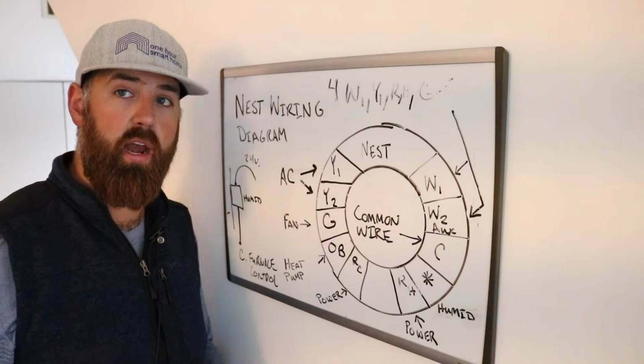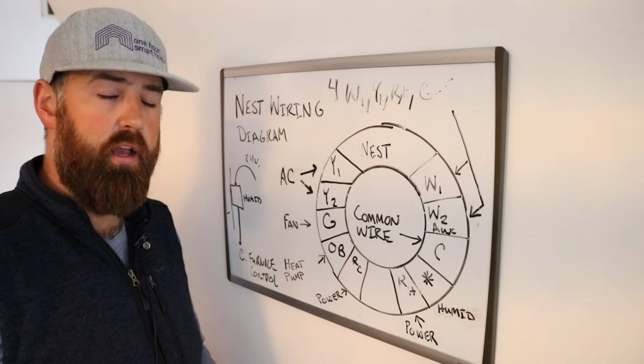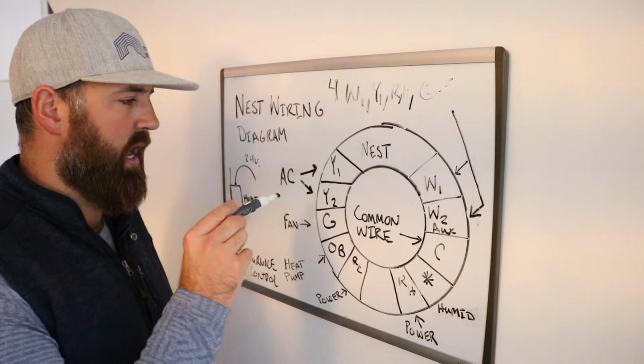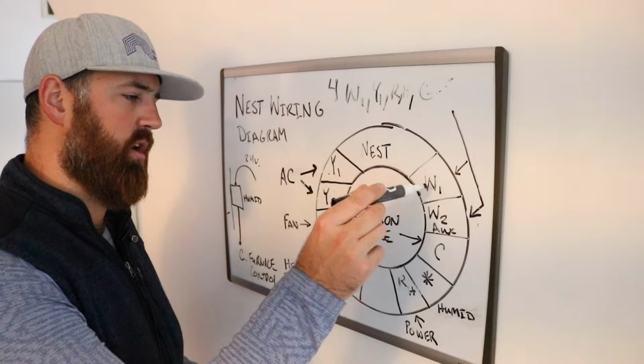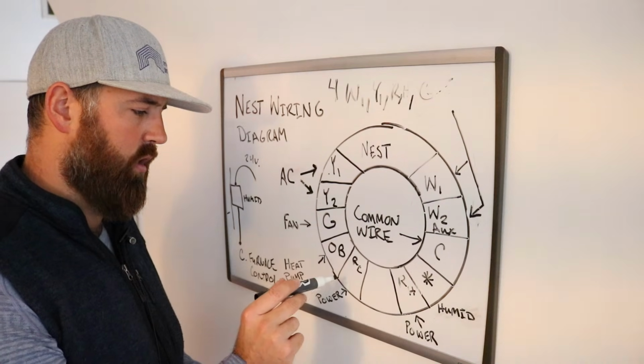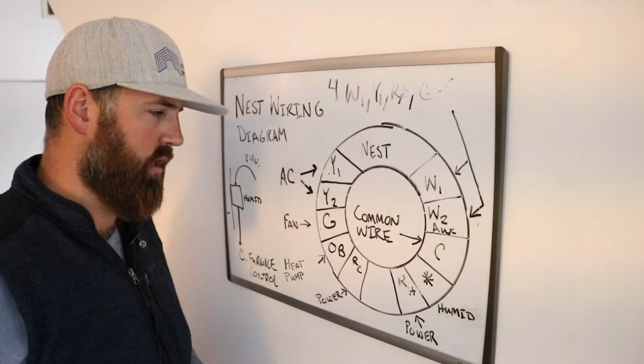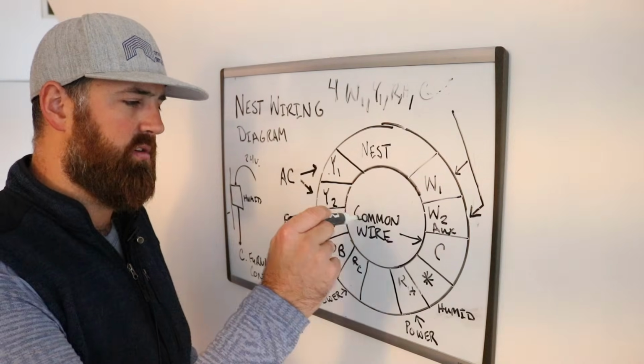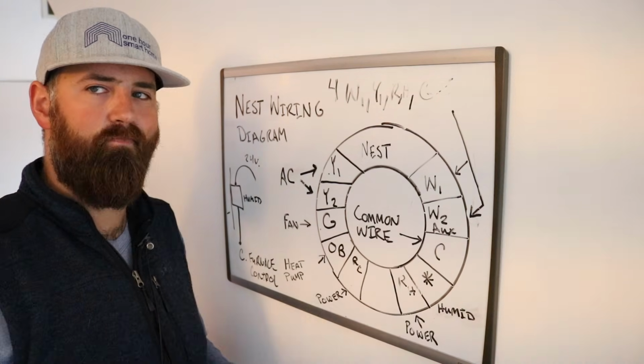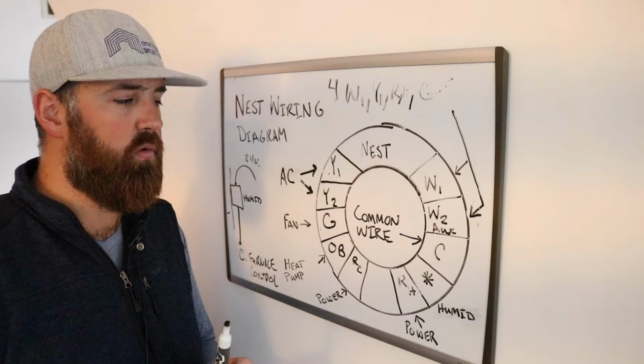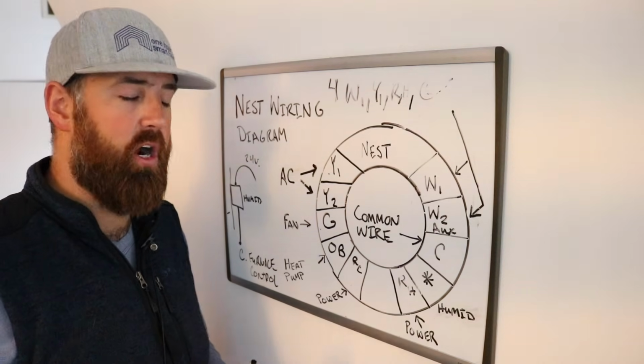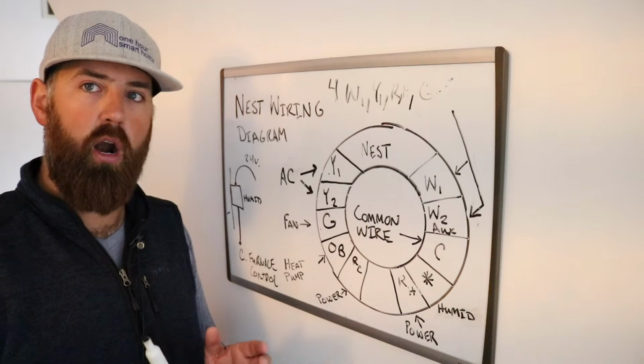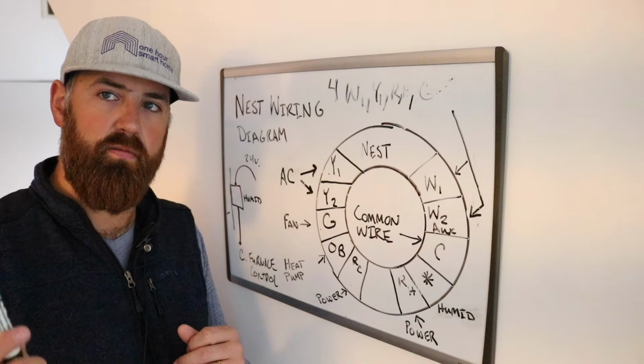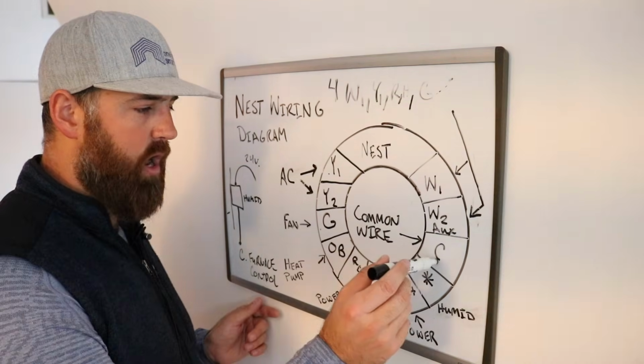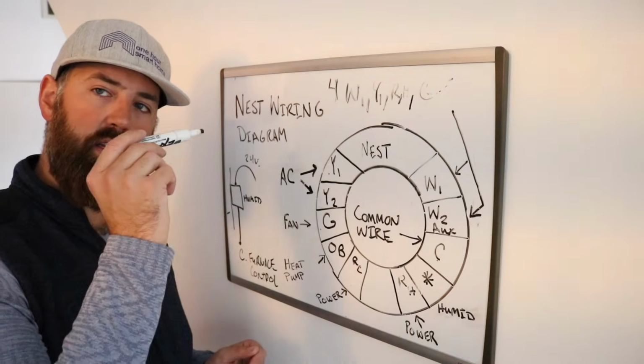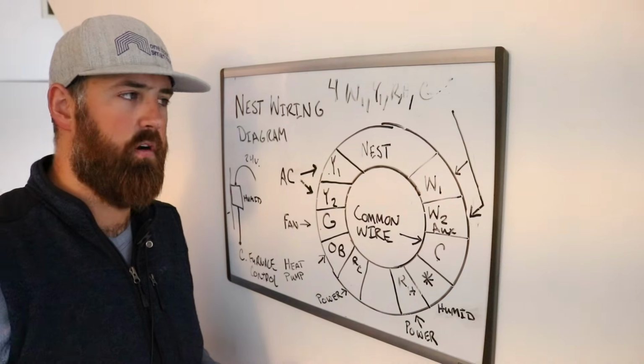Now, if you're lucky and had a common wire, an extra wire in your HVAC system, you could have Y1, W1, C, RC, and G. That gives you constant power for your Nest. A lot of people don't need it, but some do, and some have that extra wire if they had 5 wires. You need to make sure this common wire is connected inside your furnace, and this C wire at the Nest also has to be connected to the C terminal back at your furnace.